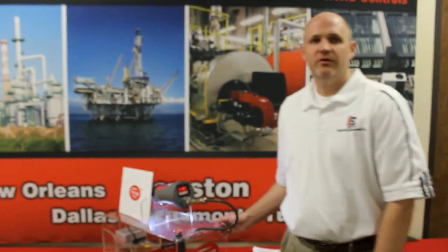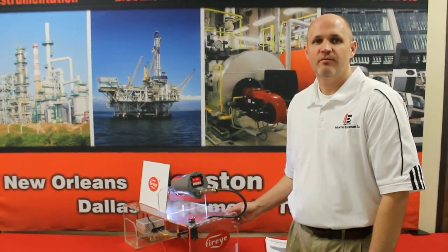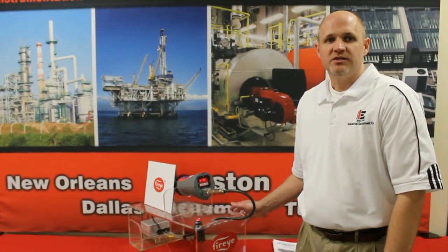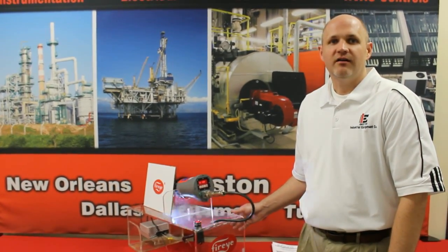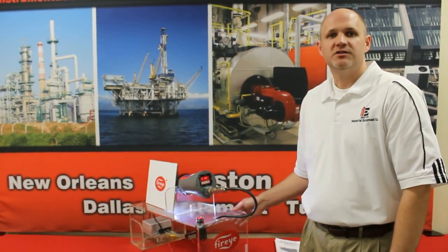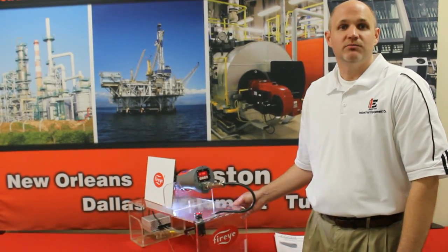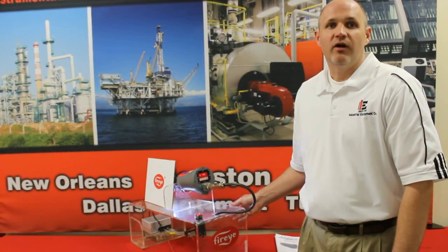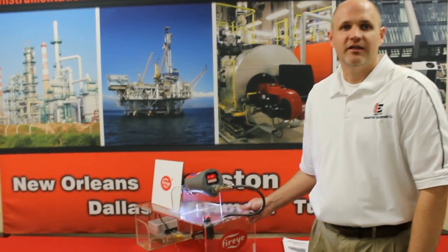That is an overview of how to set up a Fireye Insight 95 series flame scanner. After you complete the initial setup from what we just demonstrated, you may be required to go back into the flame scanner and change your UV gain or frequency settings. This demonstration was for a single burner application. If you have a multiple burner application, consult with Industrial Equipment Company or the Fireye bulletin on how to complete a setup using a multi-burner application. Thank you very much for your time.